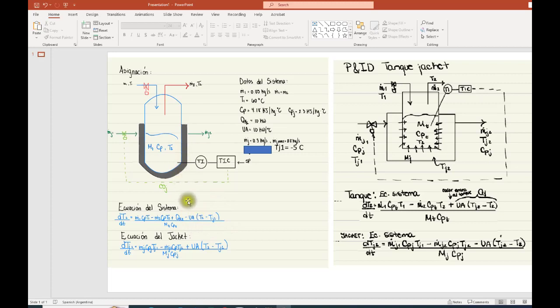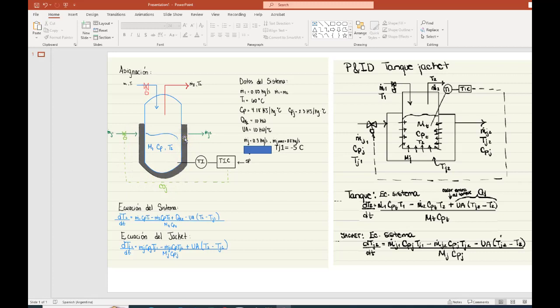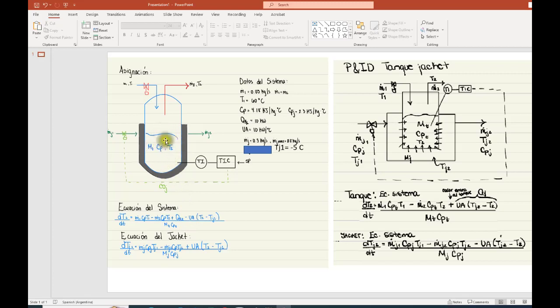Keeping Q_jacket positive means T2 is higher than Tj2 — where Tj2 is the exit jacket temperature. The assumption that the jacket temperature equals Tj2 is a simplification, but it gives us a tractable starting point with only these two differential equations. We want to keep Q_jacket positive, meaning T2 is always higher than Tj2, so that term is positive. That's the amount of heat being removed by the jacket from the vessel content — and that's why there's a negative sign in the energy balance.